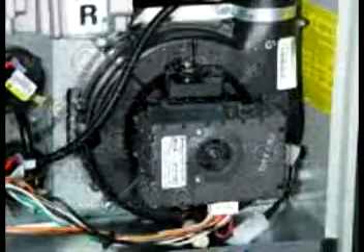Some variable speed gas furnaces use a DC drive induced draft motor that has an onboard microprocessor control. The vent pressure switches report directly to the vent motor assembly. Pressure switch status is reported to the IFC board on a communication bus between the IFC board and the microprocessor board on the vent motor. There are status LED indicator lights on the IFC that communicate diagnostic information received from the vent motor microprocessor.